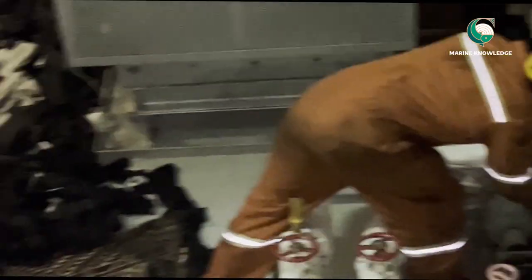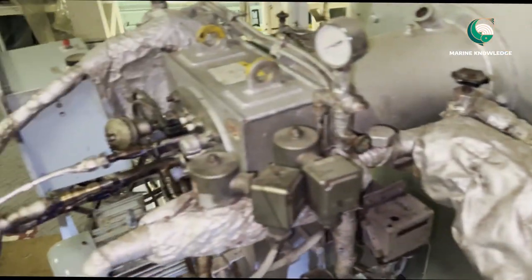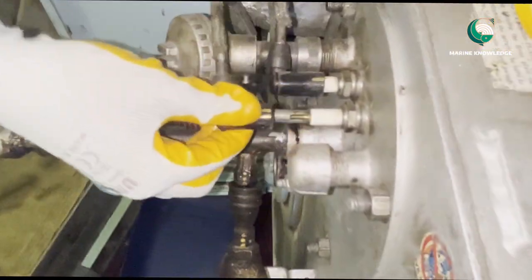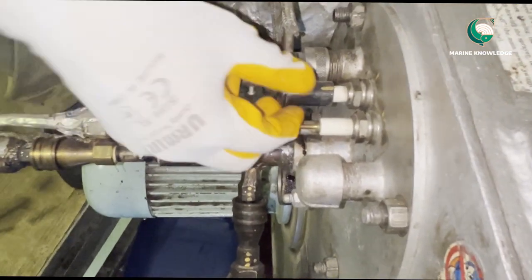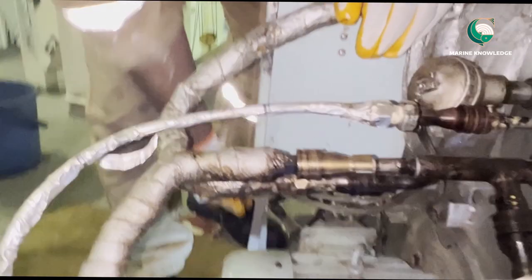As I always say, whenever you are doing the closing of valves, do not use the F-Spanner to tighten it. Always try to do hand tightening. If you use an F-Spanner there are chances of the valve getting damaged over a period of time. The next step is to remove the ignition electrode power connection.